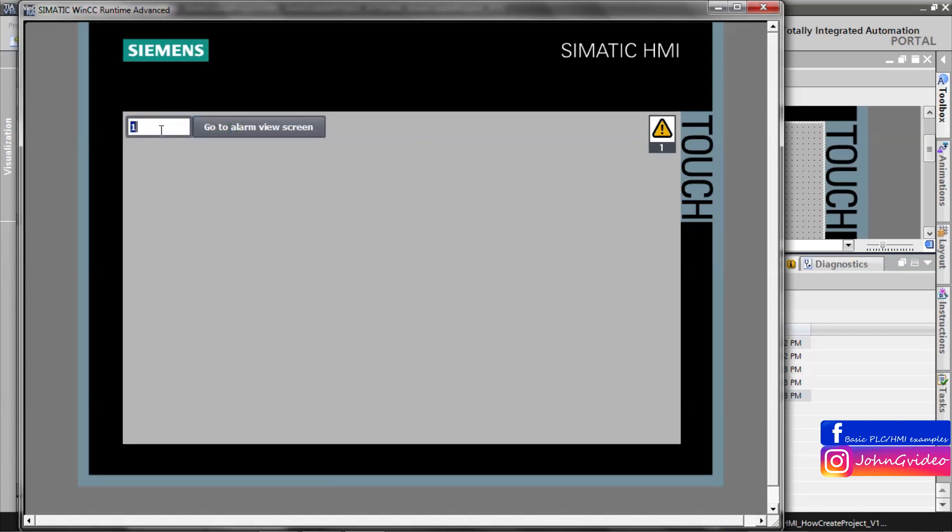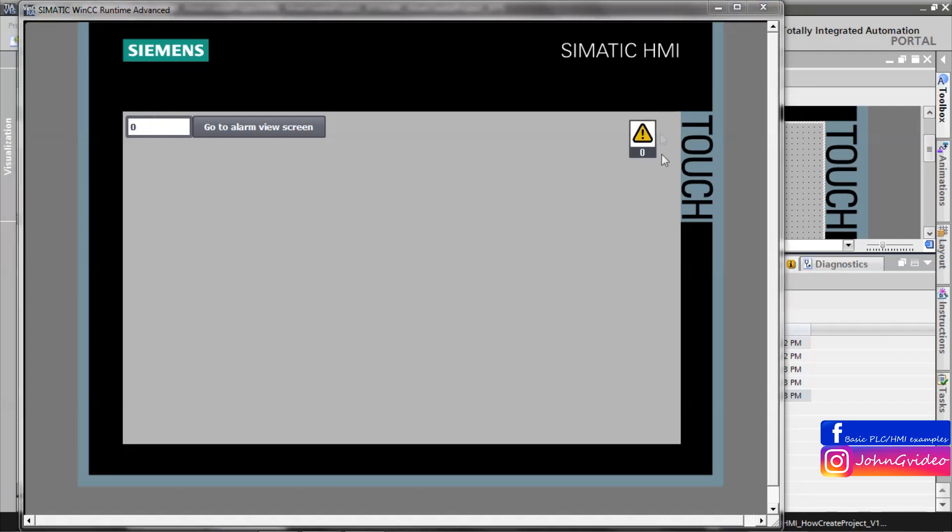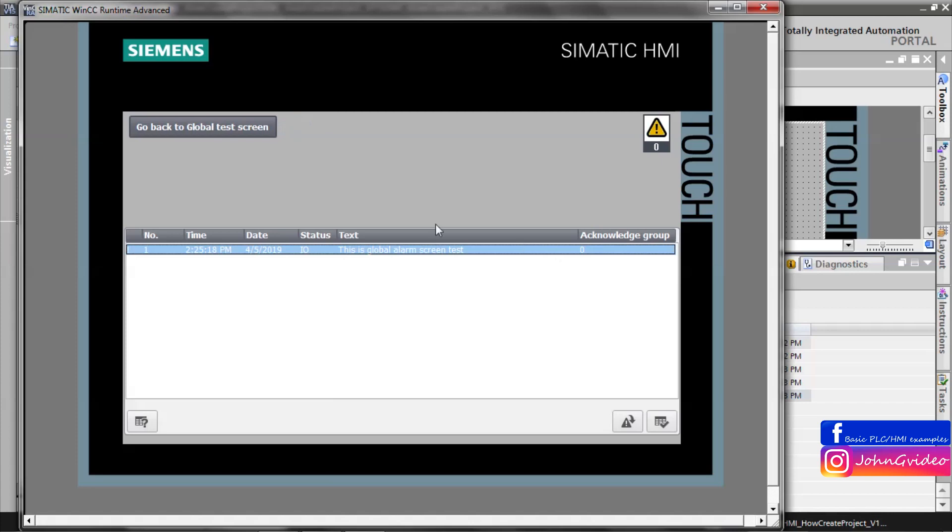We can acknowledge it but nothing happened because alarm is still active. But when we inactivate this alarm, now we don't see alarm indicator. But also if you activate the alarm and now we inactivate the alarm we still see the alarm indicator. But as you can see there is zero active alarms. This means we have some alarms which are not acknowledged and when we acknowledge it then we don't see the indicator.